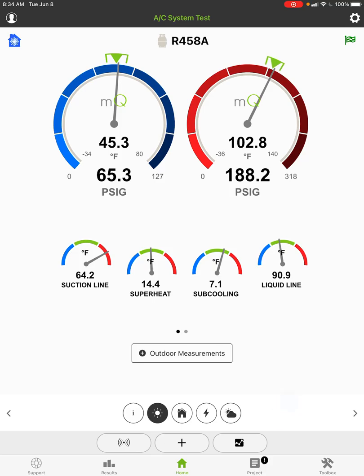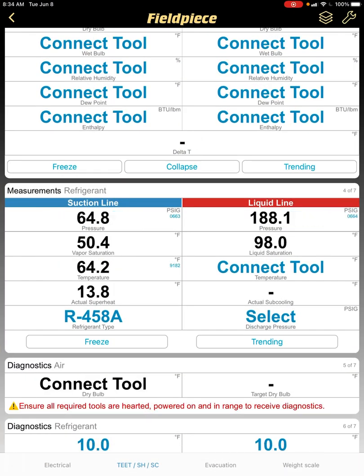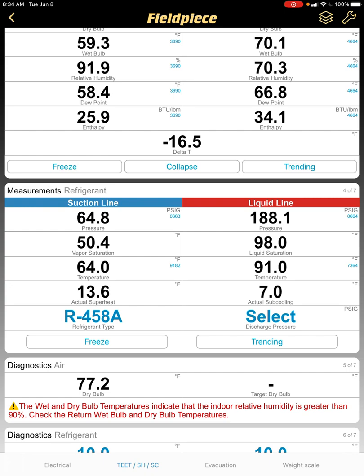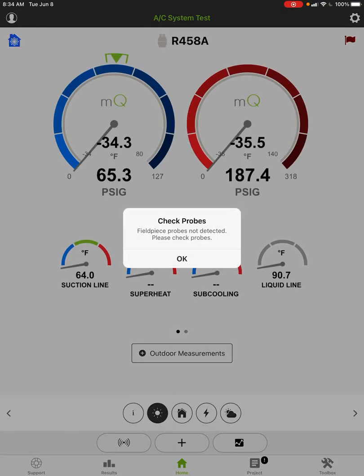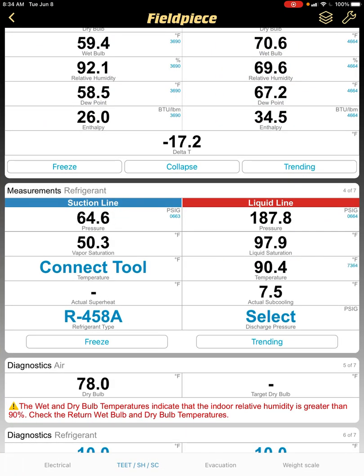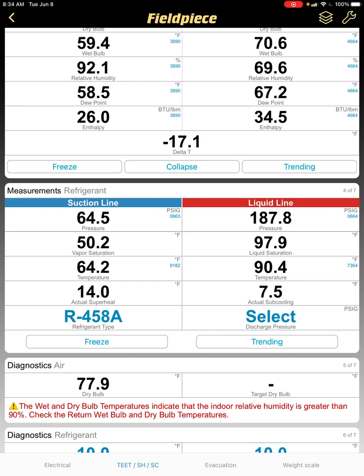If we look at the FieldPiece app — I'll just switch apps here so you can see it — you'll see that we have the same suction line temperature, but the vapor saturation temperatures are 50 and 98. Going back to MeasureQuick, we're at 45 and 102 — they're definitely different. But if we look at the superheat and subcooling at 14.3 and 7.1, and go back to the FieldPiece app, those are almost identical: 14 and 7.5.